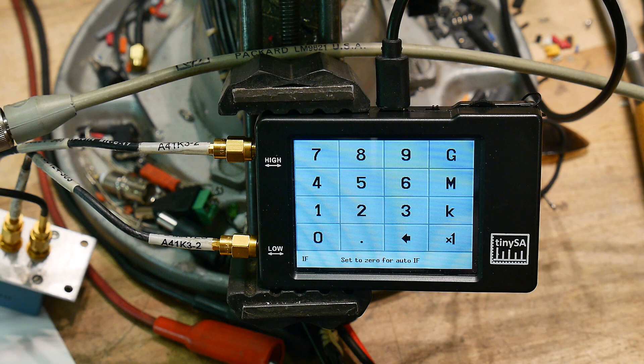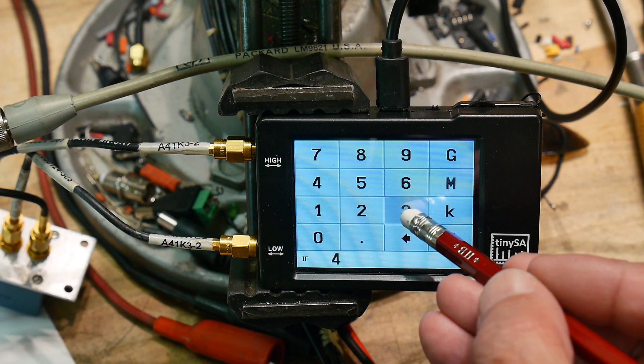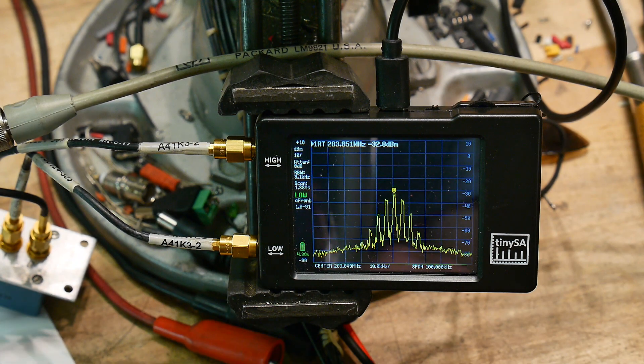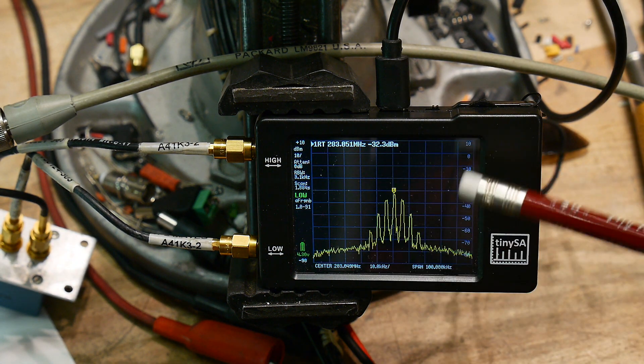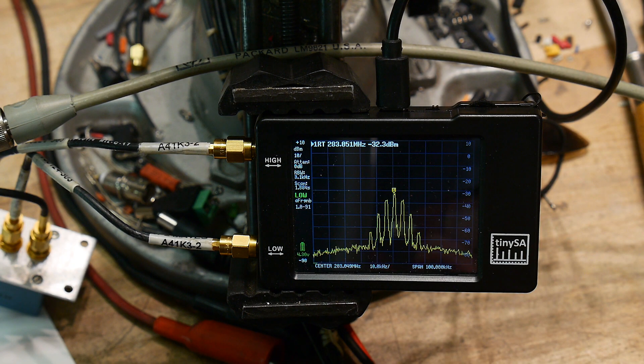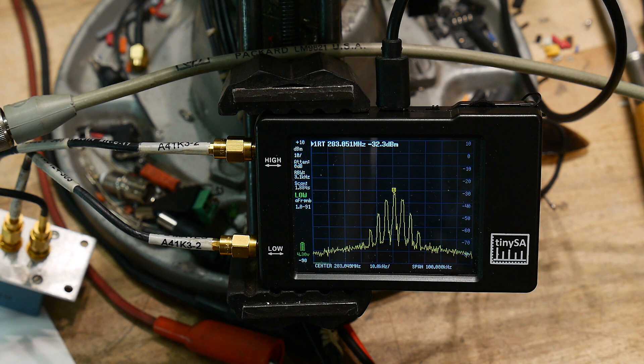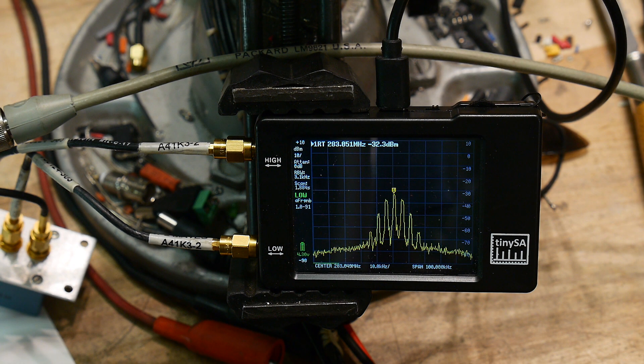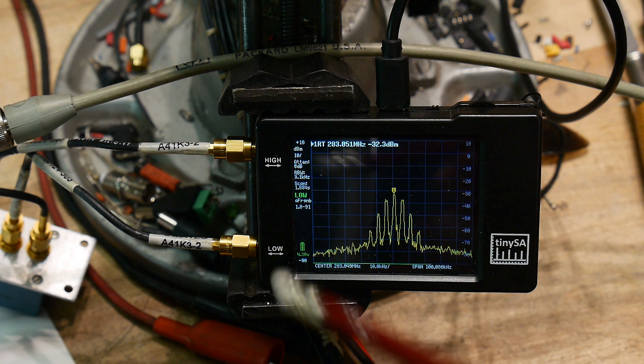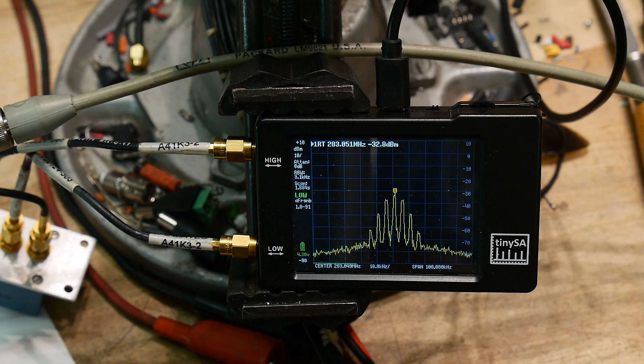So in order to use this mode, we need the IF frequency constant all the time. So we need to go into the IF frequency and we need to set it. We're going to say 433.9 MHz. And then that locks it down so it doesn't change. So you have to do those two things, turn the LO on and set the IF frequency to 433.9. And then you're ready to go. And we can measure things between 434 and 1134 MHz on the low channel by using the external mixer.